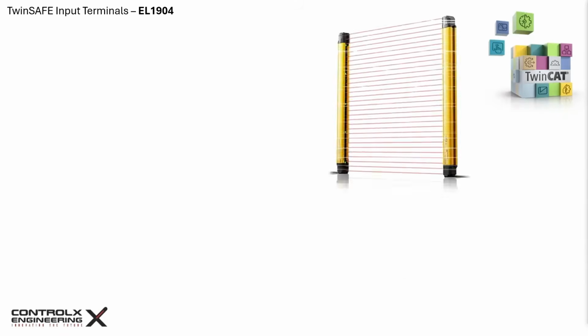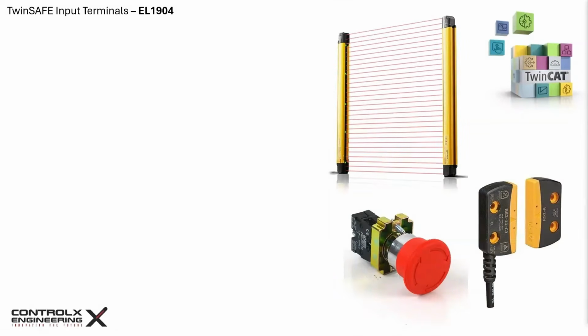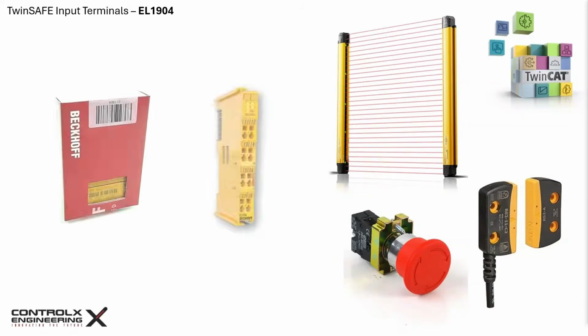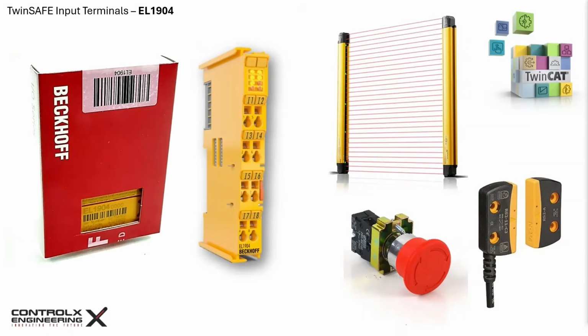The EL6910 can be considered to be the brains of the safety operations, but a brain is useless without sensors. To read the physical state of connected safety devices like e-stops, light curtains, etc., we need the EL1904 safe input terminal. This is a 4-channel safe input terminal that serves as a TwinSAFE FSoE slave. It operates on a 24-volt DC basis, but that is where the similarities to a standard input card end. The EL1904 is engineered for high-risk applications.